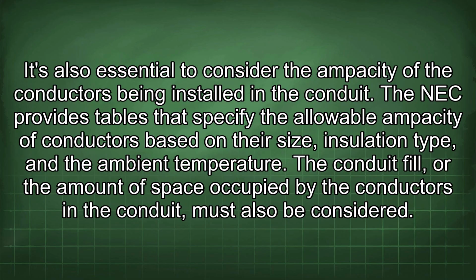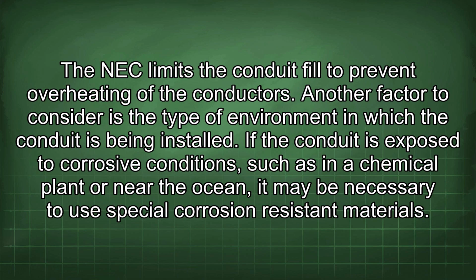It's also essential to consider the ampacity of the conductors being installed in the conduit. The NEC provides tables that specify the allowable ampacity of conductors based on their size, insulation type, and the ambient temperature. The conduit fill, or the amount of space occupied by the conductors in the conduit, must also be considered. The NEC limits the conduit fill to prevent overheating of the conductors.